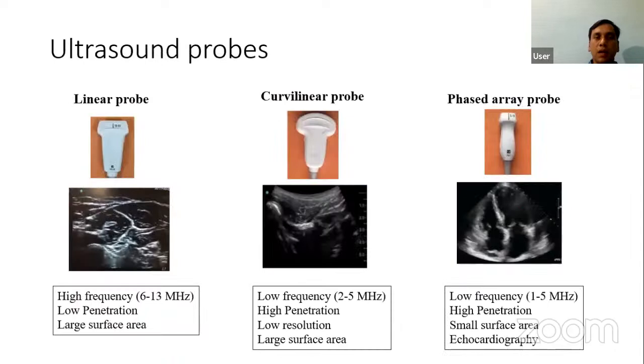Now, coming to the different ultrasound probes that we use, there are basically 3 types of probes: linear, curvilinear, and phased array probes. Linear probes, as you know, are high frequency. I already mentioned they have low penetration, but they give very good resolution and have a very large surface area. Similarly, the curvilinear probe has a frequency of around 2 to 5 megahertz. They have high penetration but give low resolution.